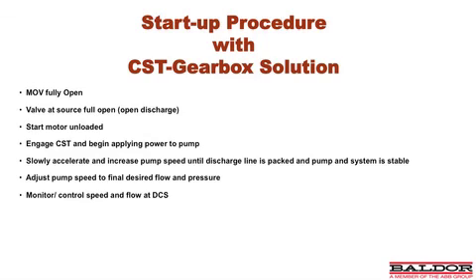So now let's look at the CST startup procedure. With the CST startup methodology, the MOV can be fully open, or in some cases they do not want the flow backflowing through the pump, so the MOV could be started closed, at which time, if that is the case, the MOV can be programmed into the CST logic. This would allow the pump speed through the CST clutch to open in unison with the MOV, thus providing a benign start.